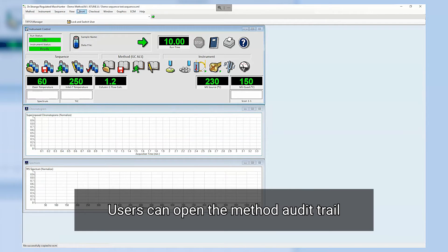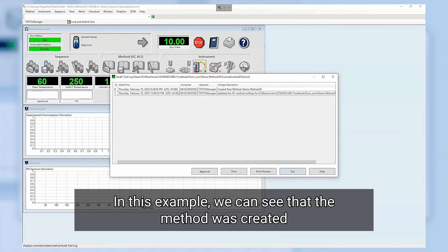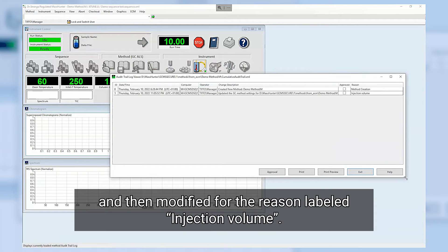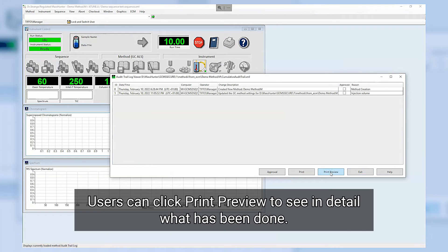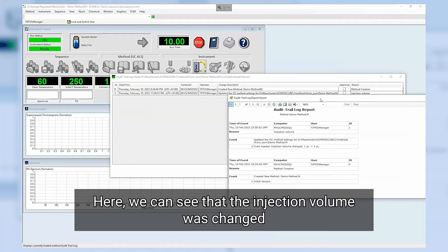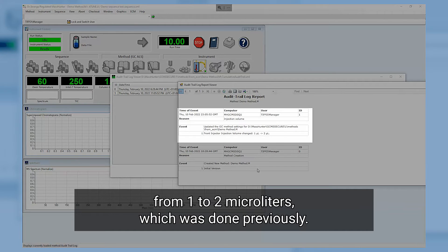Users can open the method audit trail by selecting Method then View Method audit trail. In this example we can see that the method was created and then modified for the reason labeled Injection Volume. Users can click Print Preview to see in detail what has been done. Here we can see that the injection volume was changed from 1 to 2 microliters which was done previously.